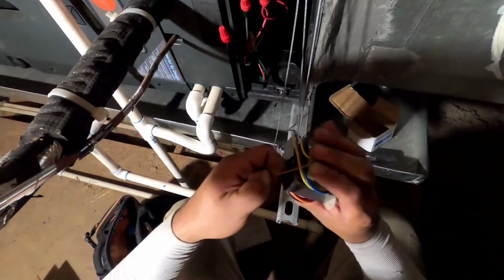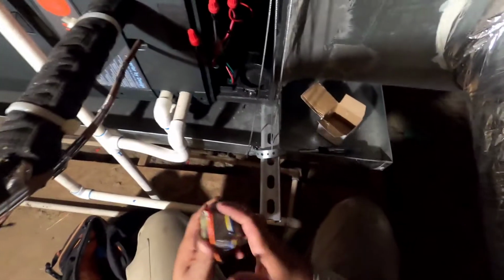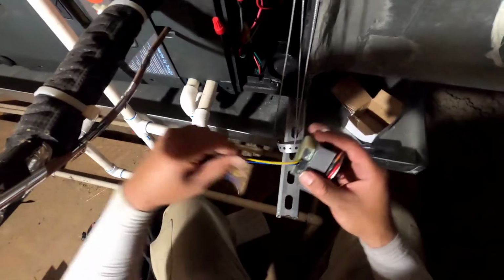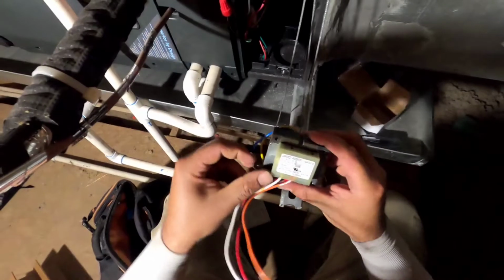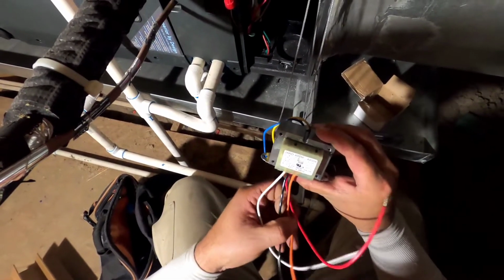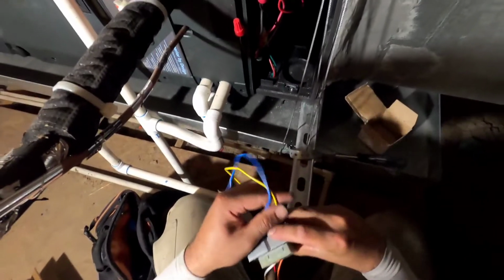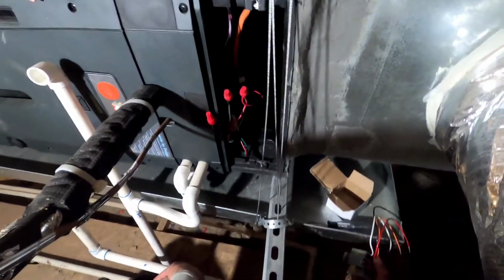The reason you need to put in a new transformer is because if you have a smart thermostat, or if you plan to put a smart thermostat on, you are going to have to put one of these in anyways, because smart thermostat uses enough low voltage as is, and if you have an air scrubber also using low voltage, it can cause the thermostat to just shut off randomly, or even the air scrubber to shut off, and neither of those is a good idea.